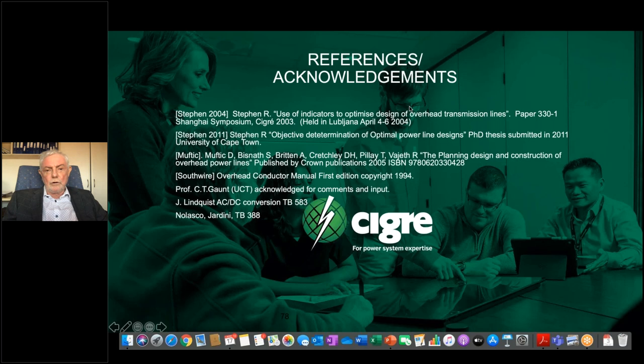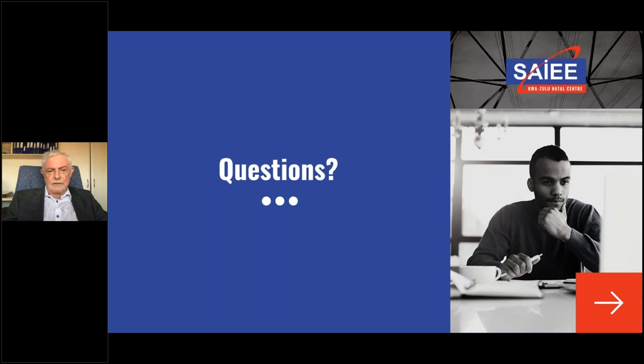Yes, there are applications, but it's mainly in the line of very specialized upgrading, or where you need a low knee point and a fairly low tension in the particular conductor. So it would be very specialized applications that you would actually consider using an ACCC or polymer core. It might be considered as a standard going forward, but which one, I'm not too sure. There are others such as the ACSS, which I would also definitely look at, especially on new lines. If you're looking, instead of using a polymer core conductor on a new line, it might actually be cheaper and more cost effective to use an ACSS conductor.